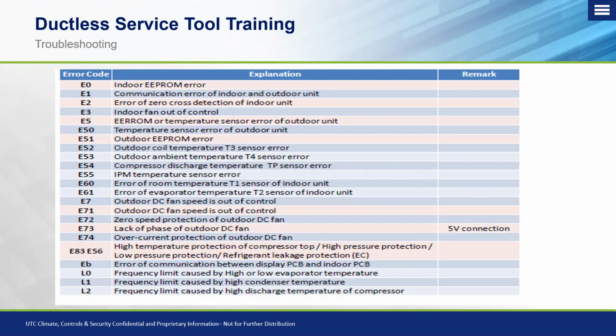So getting into the troubleshooting on here. One thing to note, and I always say this in my install and service classes, is that you always want to make sure that you're looking at a code menu like this, and you're looking at the appropriate device. So you don't want to take an error code that's on a wired wall controller and use the indoor unit error codes as a basis to confirm what an actual code means. So basically what I'm trying to tell you is that the service manual that comes with the tool is where you need to verify if you're getting an E5 or an E52 or an E54, what that actually means. So an E54, for example, on the tool would be a compressor discharge temperature protection.